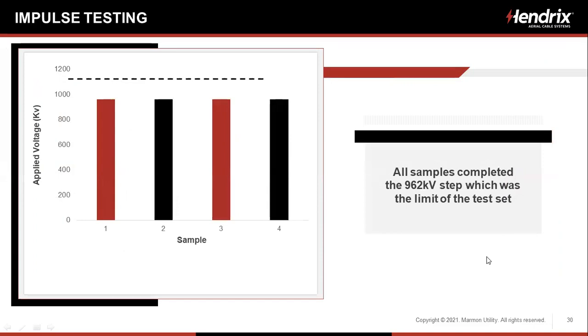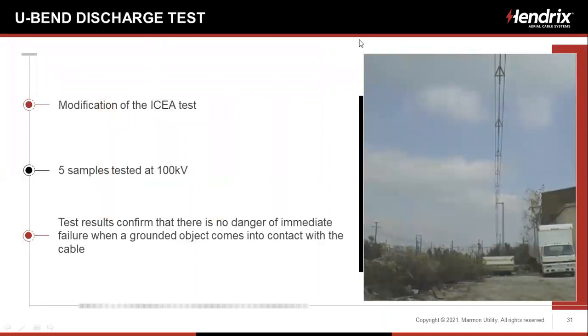We then took samples in and did the test with the Marx generator, the impulse generator, if you will. We had 4 samples that we tested, could not break them down. They all completed the 962 kV step, which was the limit of that impulse generator. So the bad news is I can't tell you the BIL of that cable. The good news is that I can tell you that it's in excess of 962 kV. Again, that is the BIL of that 69 kV cable. The BIL of the system is going to be much higher because you're going to have to add in the BIL of the spacer in the air or whatever distance you are to the ground plane, in which case here is the messenger.